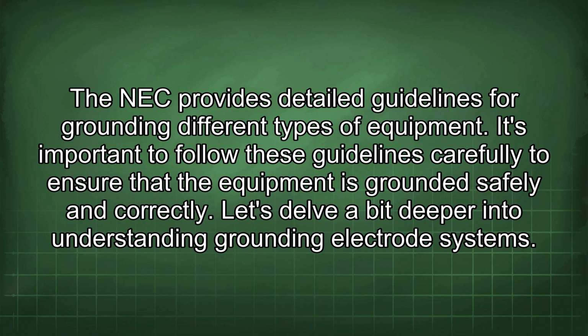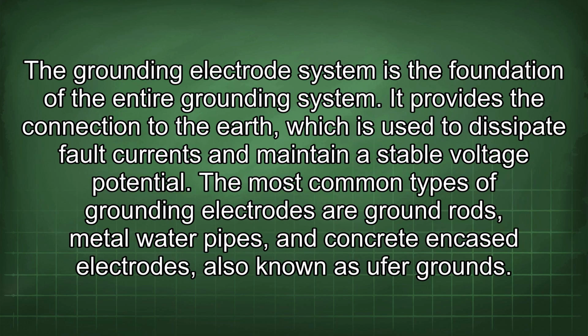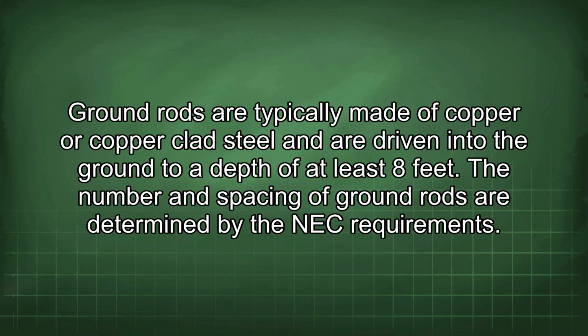Let's delve a bit deeper into understanding grounding electrode systems. The grounding electrode system is the foundation of the entire grounding system. It provides the connection to the earth, which is used to dissipate fault currents and maintain a stable voltage potential. The most common types of grounding electrodes are ground rods, metal water pipes, and concrete encased electrodes, also known as UFER grounds. Ground rods are typically made of copper or copper-clad steel and are driven into the ground to a depth of at least 8 feet.